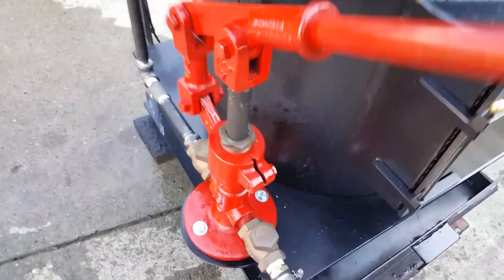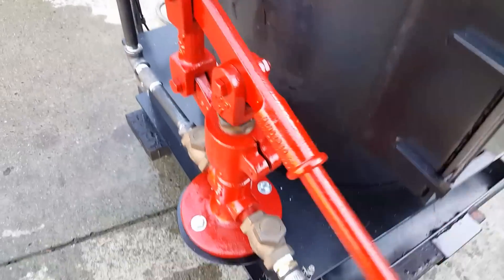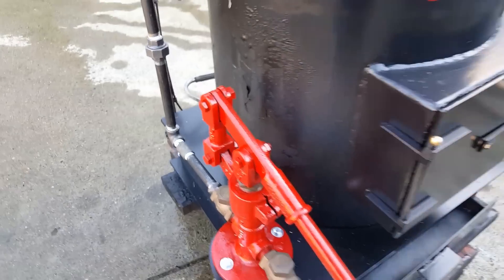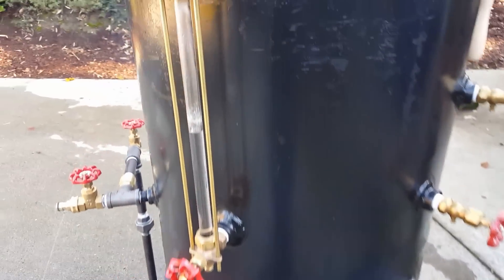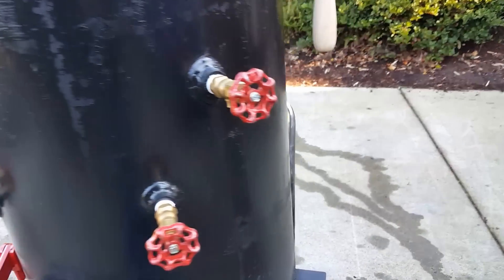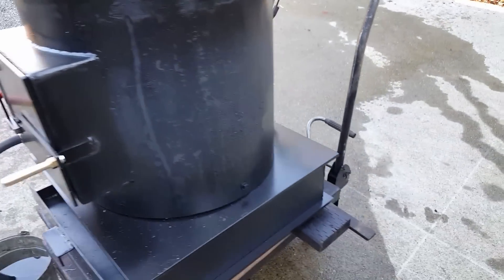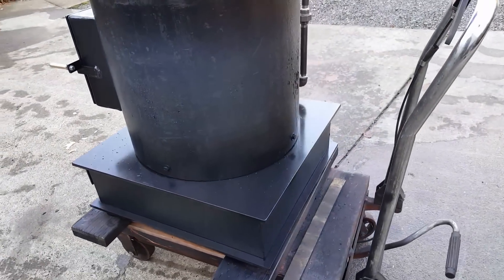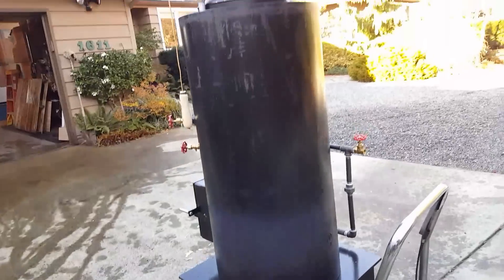Big one inch ram on it — there you can hear it working now. Moves a lot of water. Water sight glass, try-cocks. Base is 24 square, total height is 82.